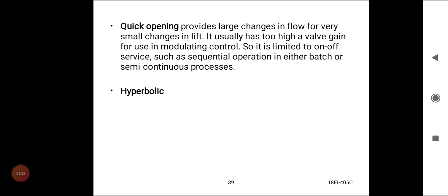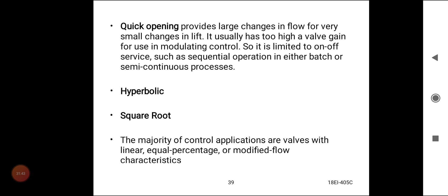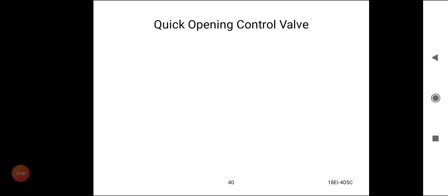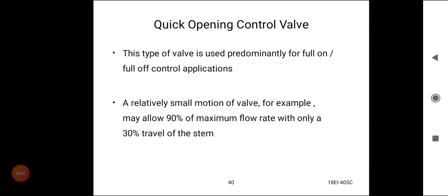Hyperbolic, square root. The majority of the control applications use valves with linear, equal percentage or modified flow characteristics. Quick opening control valve: this type of valve is used predominantly for full on, full off control applications. A relatively small motion of the valve, for example, may allow 90% of maximum flow rate with only 30% travel of the stem.